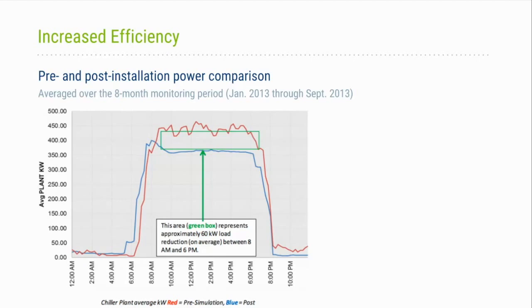The other thing of note is that with the improved software, the blue line is the post data performance. It shows an earlier startup in the morning around 5 a.m., and then a slightly higher elevated consumption around 7 a.m., but then a significant decrease throughout the day. Primarily we attribute that to the pump savings. Let's go to the next slide.